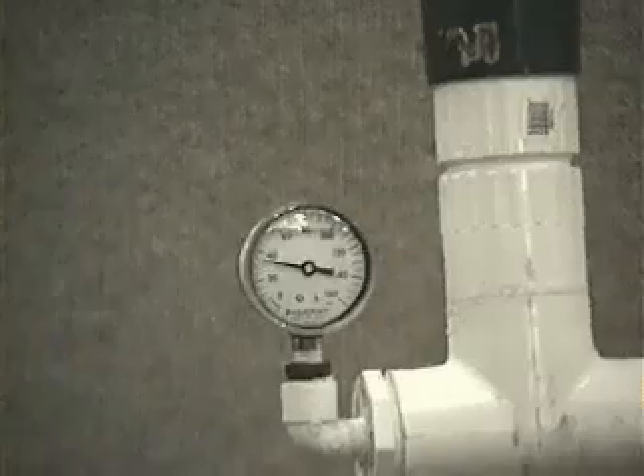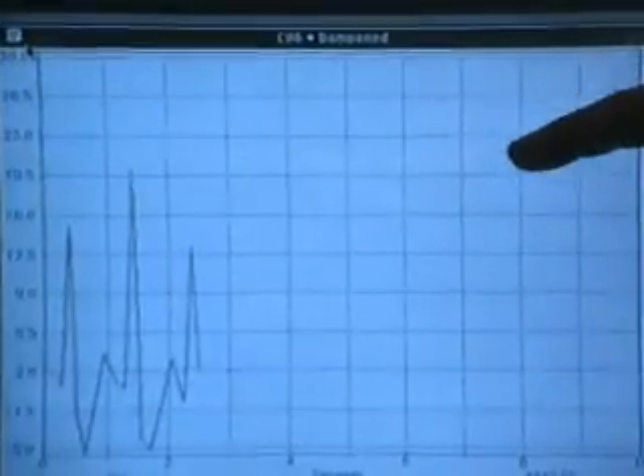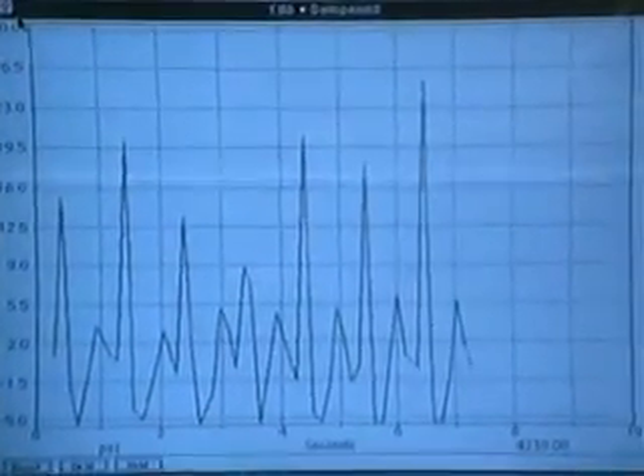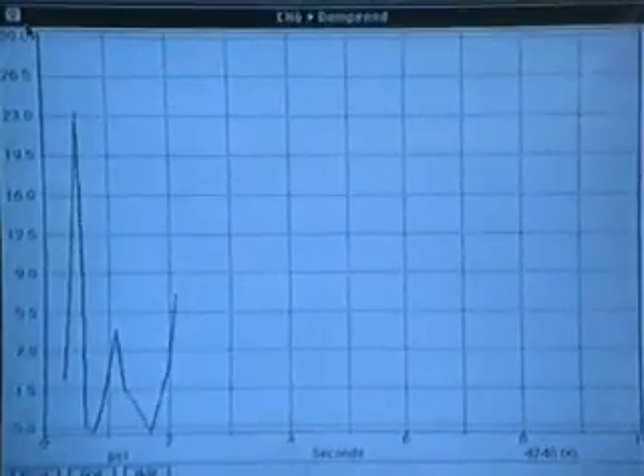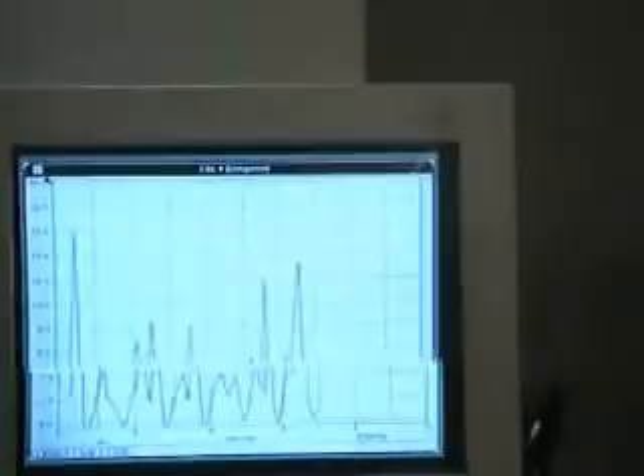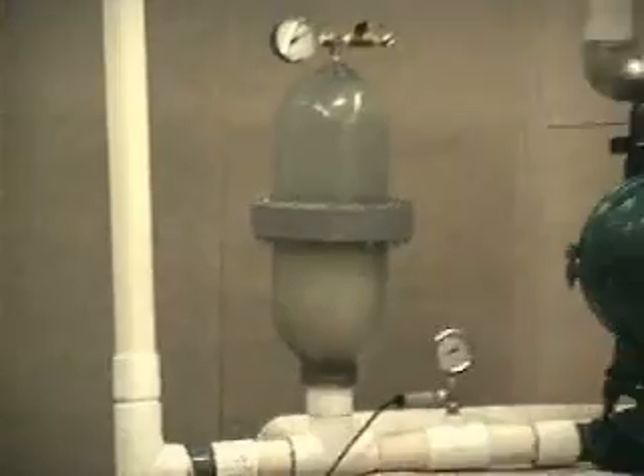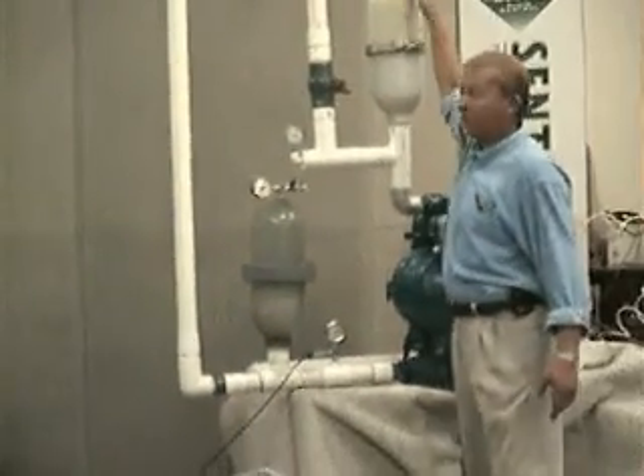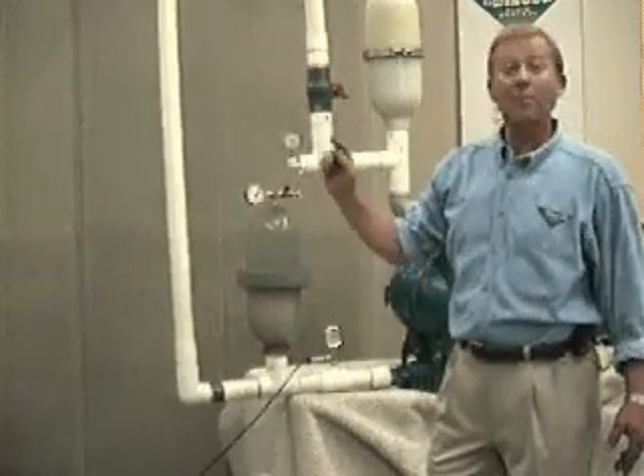The inlet side is still shaking violently, and you'll notice on the transducer that the pressure spikes are reaching as high as 19 psi. Now, most air-operated diaphragm pumps tell you in their instructions not to exceed 15 psi with rubber diaphragms or 10 psi with Teflon diaphragms. So you can see that we can be doing damage to the diaphragms with this kind of pressure spike.